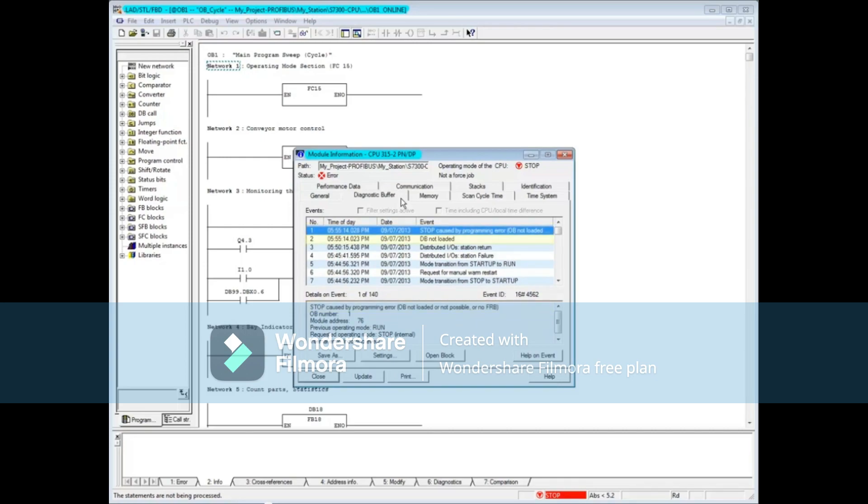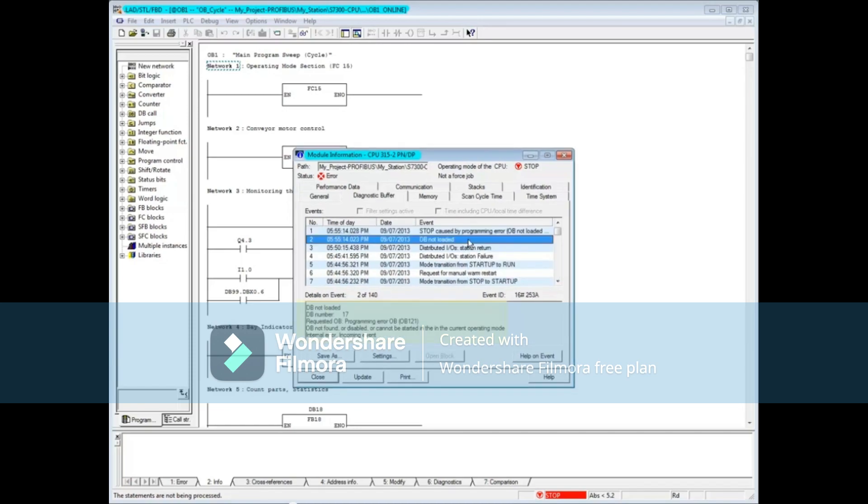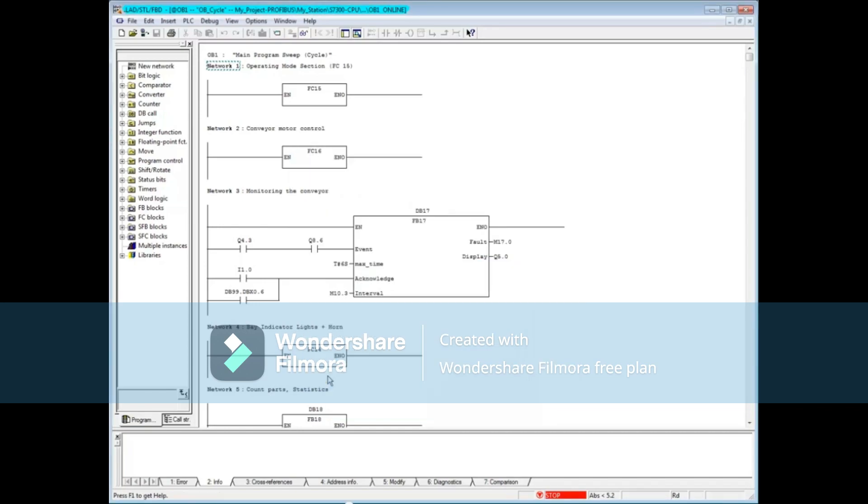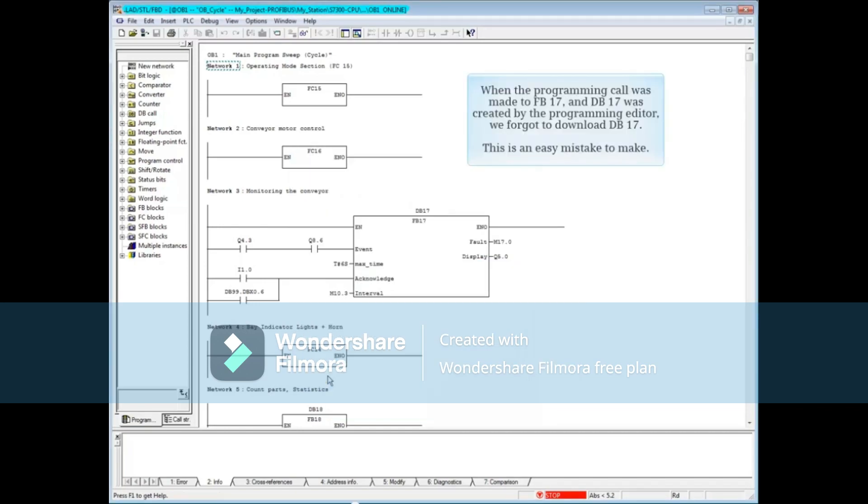Click on the diagnostic buffer tab. Message 1 tells you the CPU has gone to stop. Message 2 tells you a data block is not loaded. Click on message 2. In the details section, you can see that the data block not loaded is DB 17.